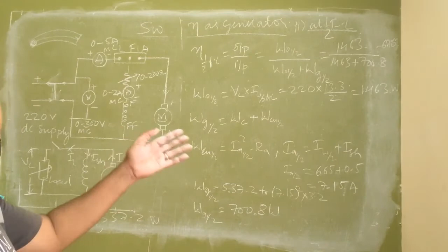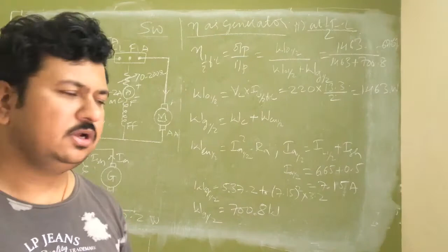So this is how you have to calculate the efficiency of a generator in Swinburne's test at any load. Simply, if you take 25%, multiply the line current IL by 0.25, 13.3 into 0.25; 75%, 13.3 into 0.75; 80%, 13.3 into 0.8; 90%, 13.3 into 0.9. Any percentage of load you can calculate. But you have to take that load current into consideration in the output also. Many a time the mistake you people make is taking the output as VL into IL with 13.3, but calculating the losses with the half load current. The efficiency will then be more than the full load efficiency, which won't happen. So you should be careful about these aspects.